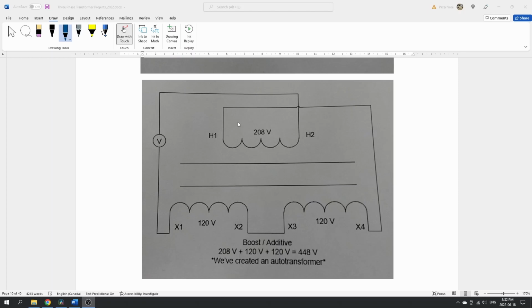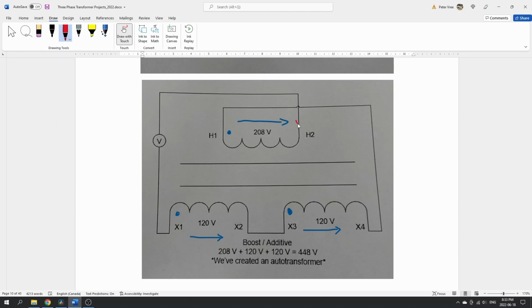Okay, so let's see. I'm going to arbitrarily put in some lines here to denote a magnetic field, just an instantaneous magnetic field. Of course, the magnetic fields are bouncing back and forth 60 times a second, but I'm just showing that H1 and X1 have the same relative polarity, and H1 and X3 have the same relative polarity. I've got my meter connected up right here. So I've got one meter lead right here, and I've got another meter lead right here.